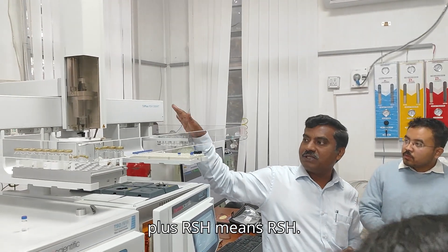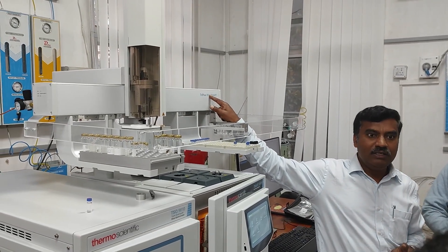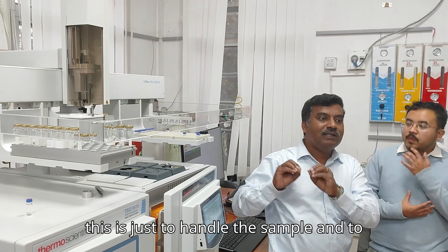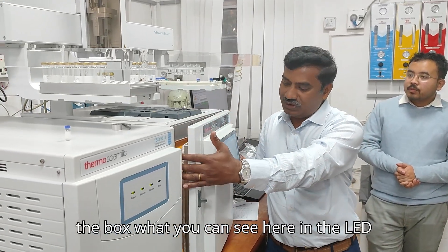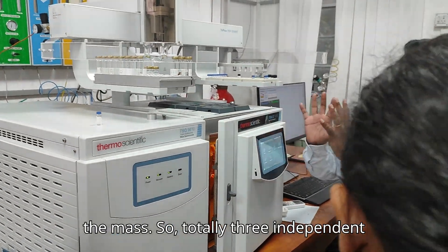TriPlus RSH stands for RSH — robotic sample handling. So robotic sample handling is all about auto-sample or auto-inject. This is just to handle the sample and inject it into the GC system. Separation happens in the GC. What you can see here is the LED screen — this is just a box. So totally three independent devices.